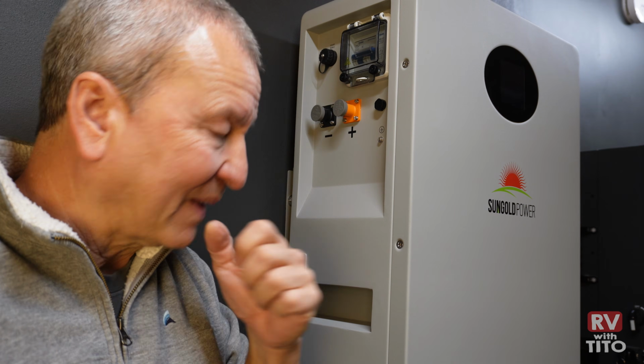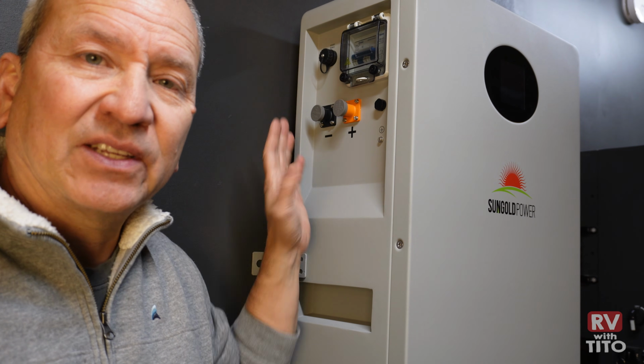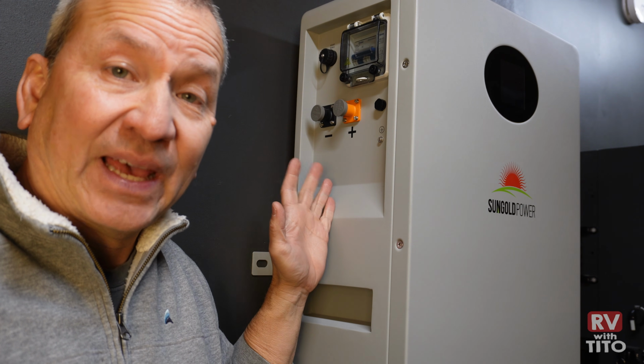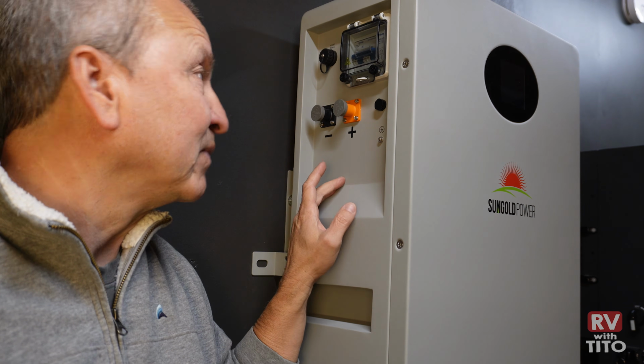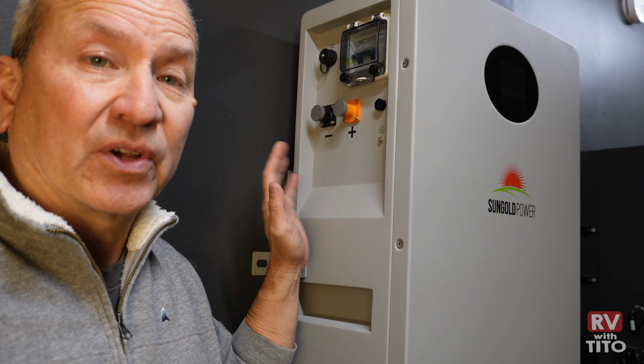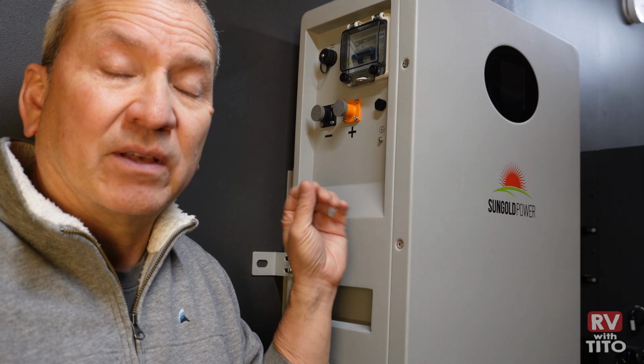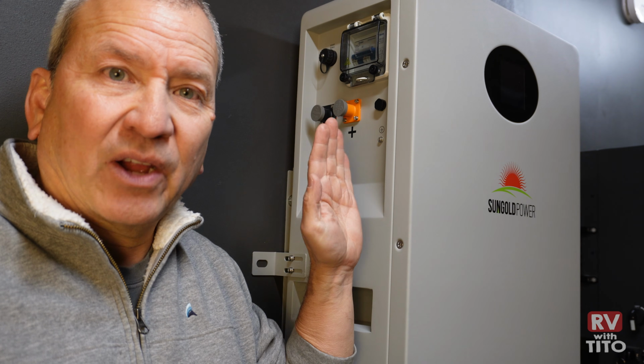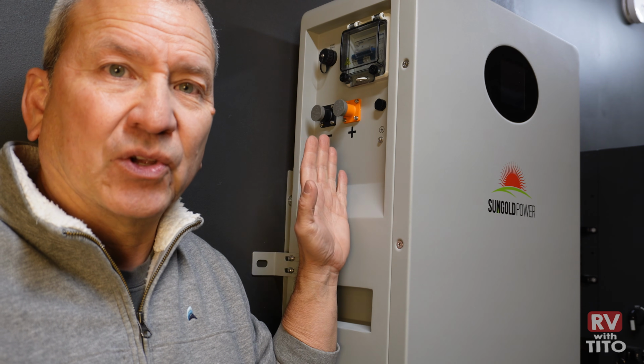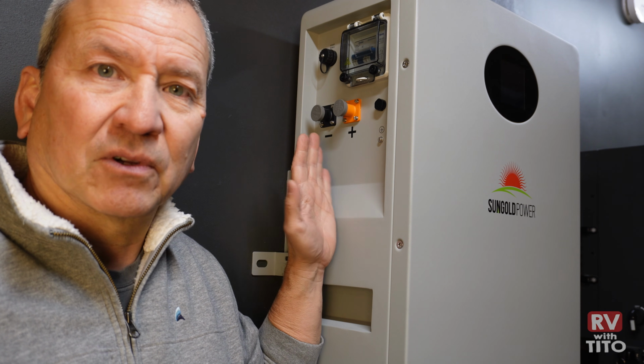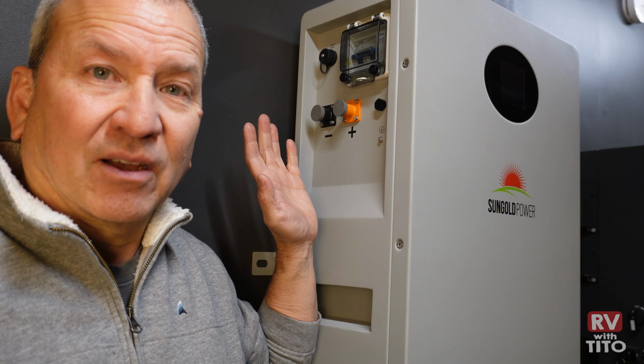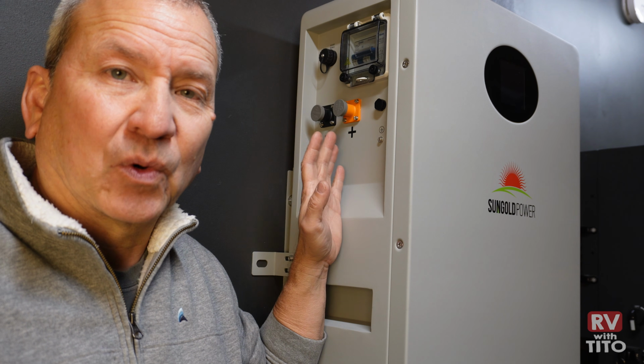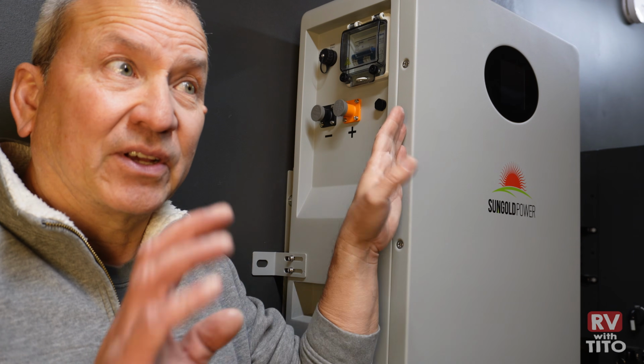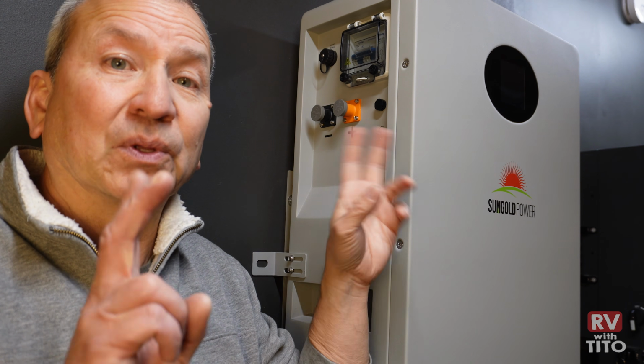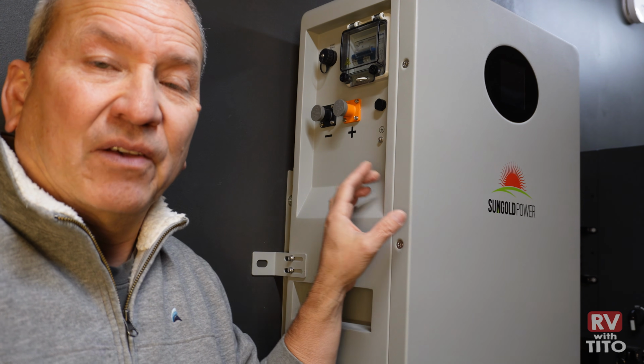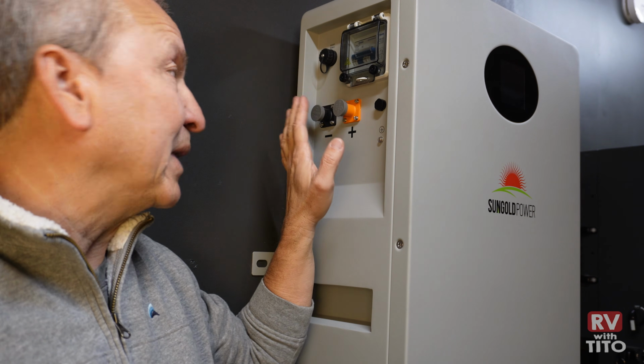Now I should also mention, if you're connecting to an inverter that doesn't have a CAN port and only has RS-485, you're going to have to probably create a cable and wire it specifically for your inverter, and it should come with specifications for how to wire the RS-485 cable for that inverter. Typically you'll have a different configuration on both sides of the cable, one for the inverter side, one for the battery side.